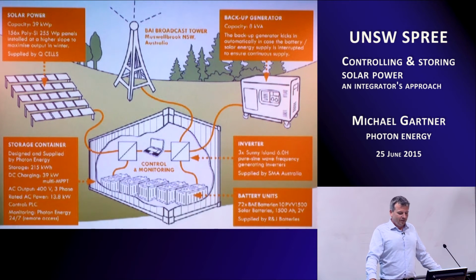Now, what happens when we don't have enough solar potential and we do have weather events? We've been monitoring the system for about the last 6 months, and we've realised that when we have long weather events, the backup generation simply has to kick in. There are two reasons for the backup generation: one is to maintain redundancy in the system, because you have to provide power, but also you want to protect the batteries. So you're looking at a depth of discharge at around a 30% level of charge in the batteries, where the generator will kick in to preserve the life of the batteries.